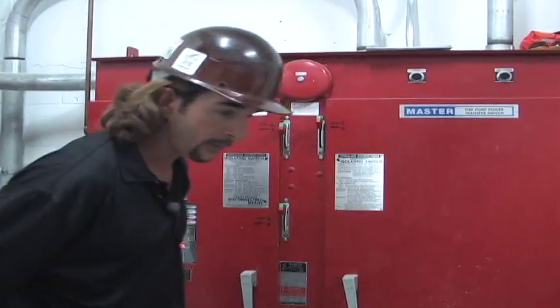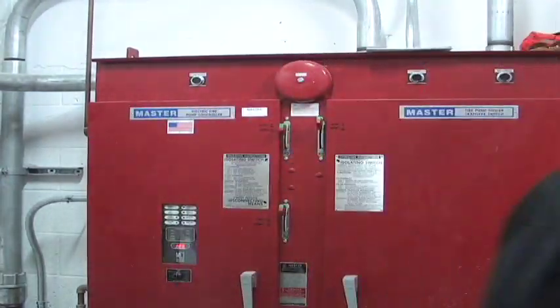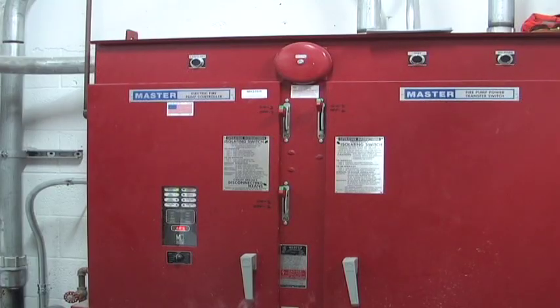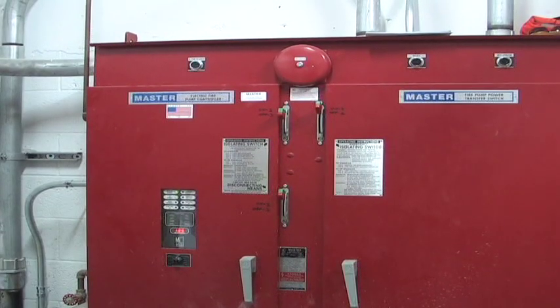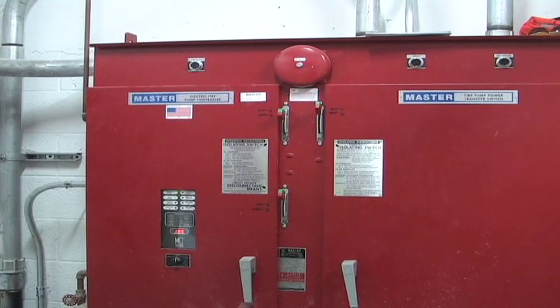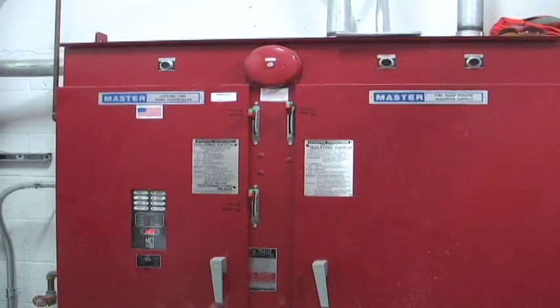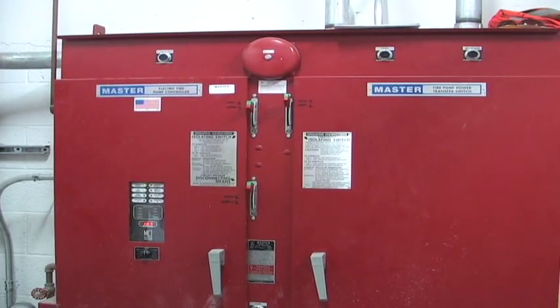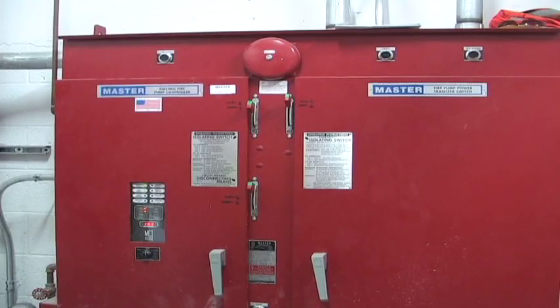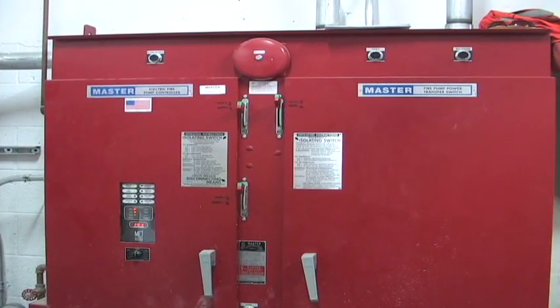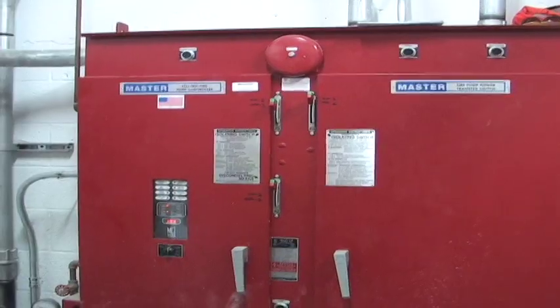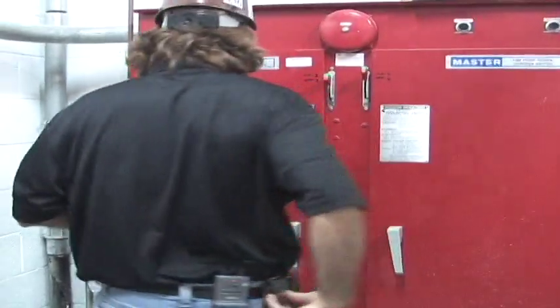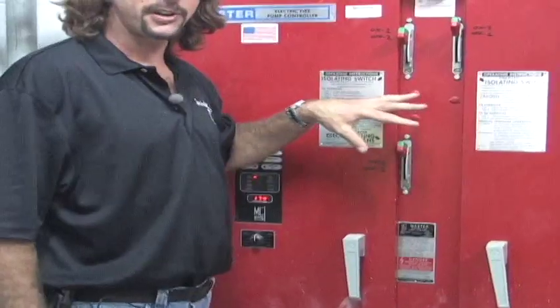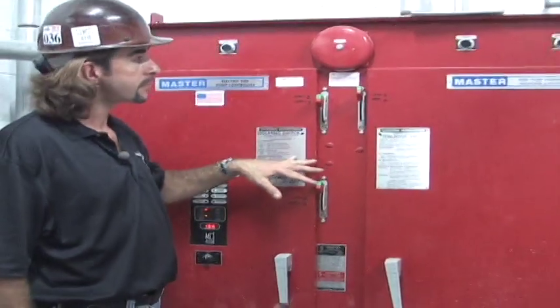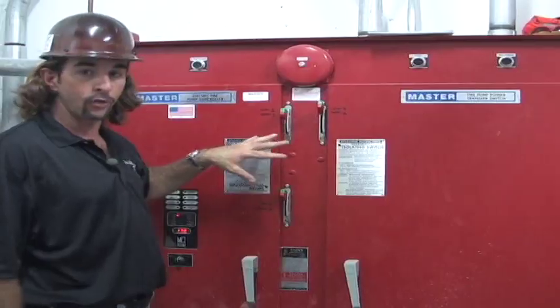So we're going to open this valve over here. You can just keep looking right here at this control. I'm going to open this valve real fast. Now our fire pump has started on a low pressure start. You've got normal power running it.